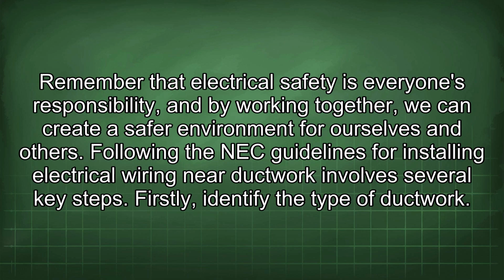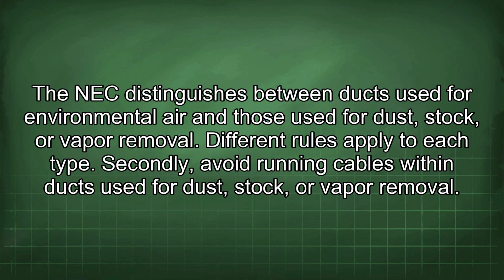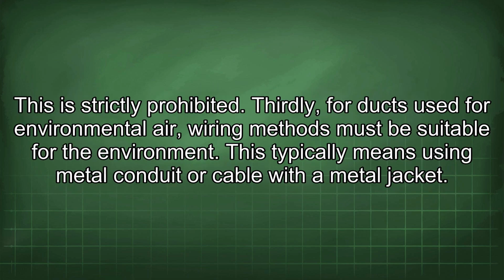Following the NEC guidelines for installing electrical wiring near ductwork involves several key steps. Firstly, identify the type of ductwork. The NEC distinguishes between ducts used for environmental air and those used for dust, stock, or vapor removal. Different rules apply to each type. Secondly, avoid running cables within ducts used for dust, stock, or vapor removal. This is strictly prohibited. Thirdly, for ducts used for environmental air, wiring methods must be suitable for the environment.